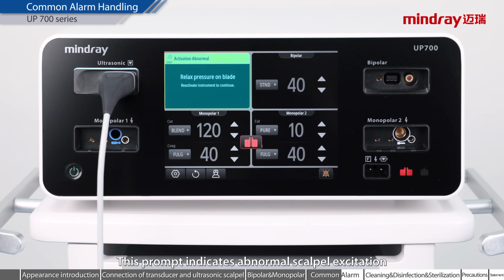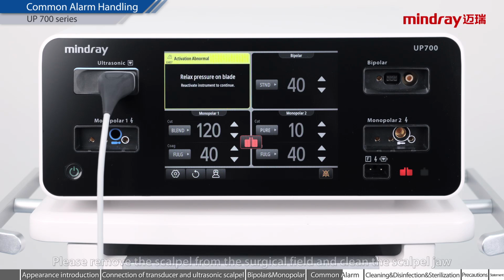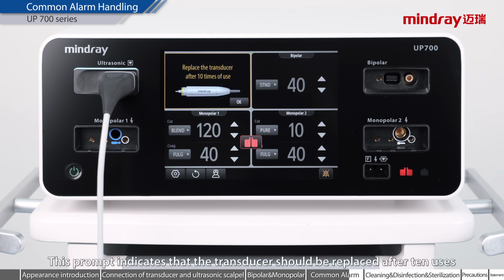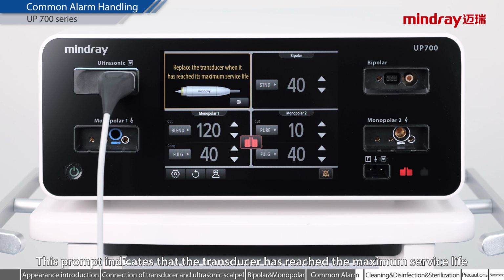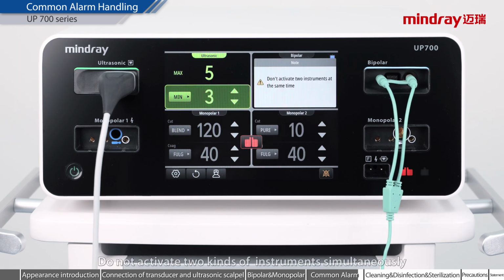This prompt indicates abnormal scalpel excitation. Please remove the scalpel from the surgical field and clean the scalpel jaw. This prompt indicates that the transducer function is abnormal. Please replace the transducer. This prompt indicates that the transducer should be replaced after 10 uses. This prompt indicates replacing the transducer after 1 use. This prompt indicates that the transducer has reached the maximum service life. Please replace it. Do not activate 2 kinds of instruments simultaneously.